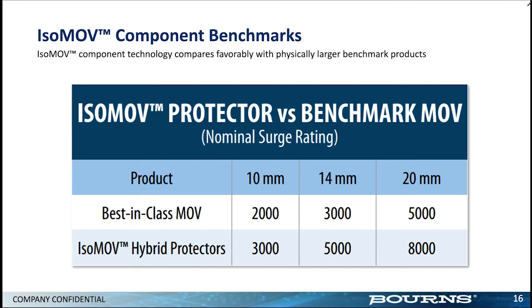So that spark over voltage, the voltage at which the GDT triggers, changes with the rise time. And this is in the data sheet. And they can go down to less than 100 volts or so, depending upon which part you pick. So for slow rates of rise, the GDT will be able to keep up, and that front end spike will drop. It'll still trigger.